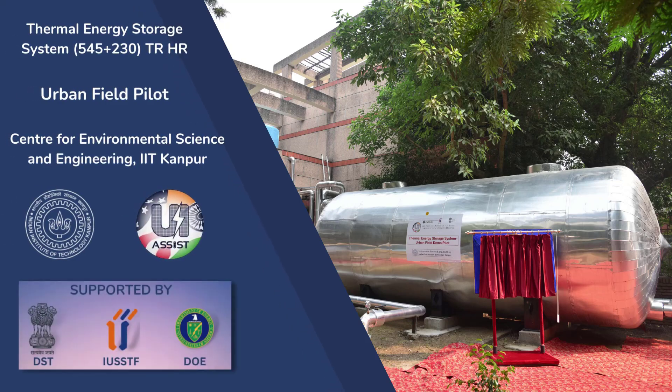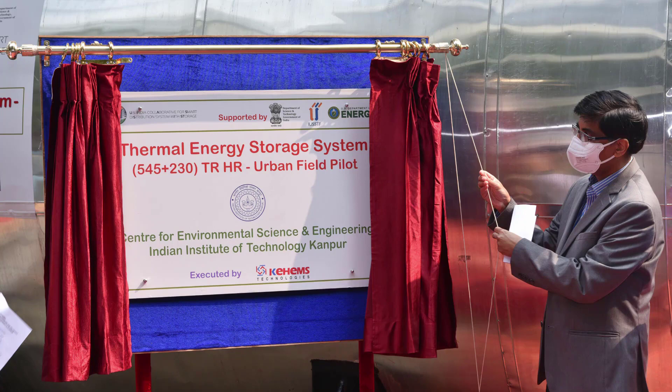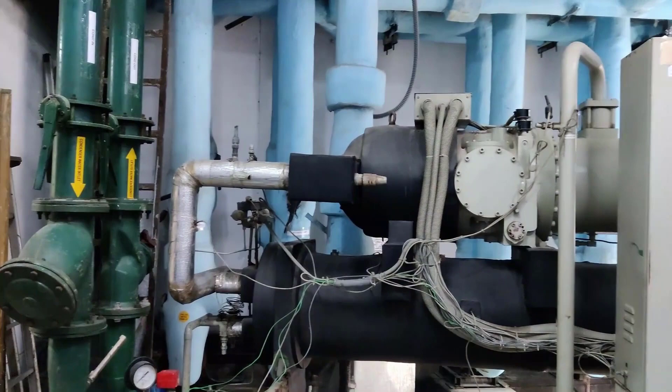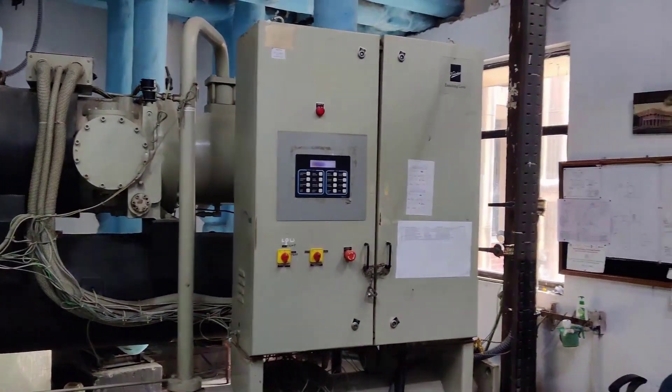As part of the implementation of our UI Assist project, a thermal energy storage system has been installed in the Center for Environmental Science and Engineering building to run the air conditioning load of the CESE building. The system has a total capacity of 775 TRHR, which can run the building's air conditioning load for almost 8 to 10 hours.